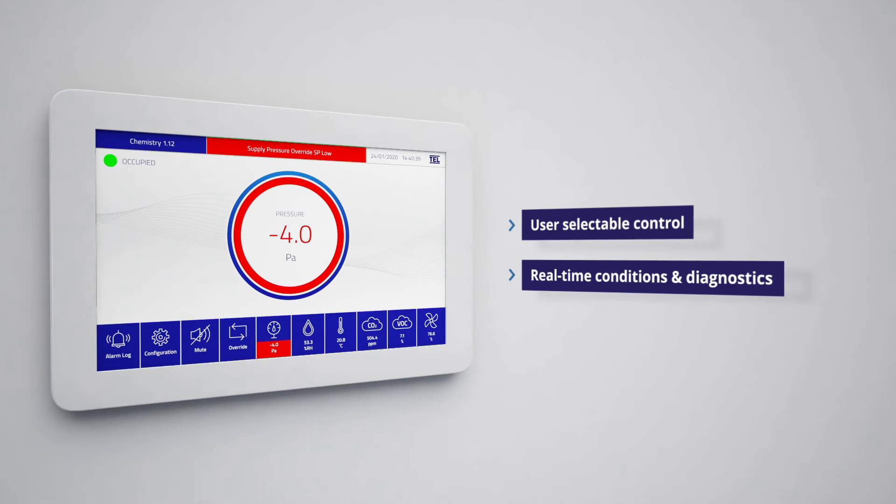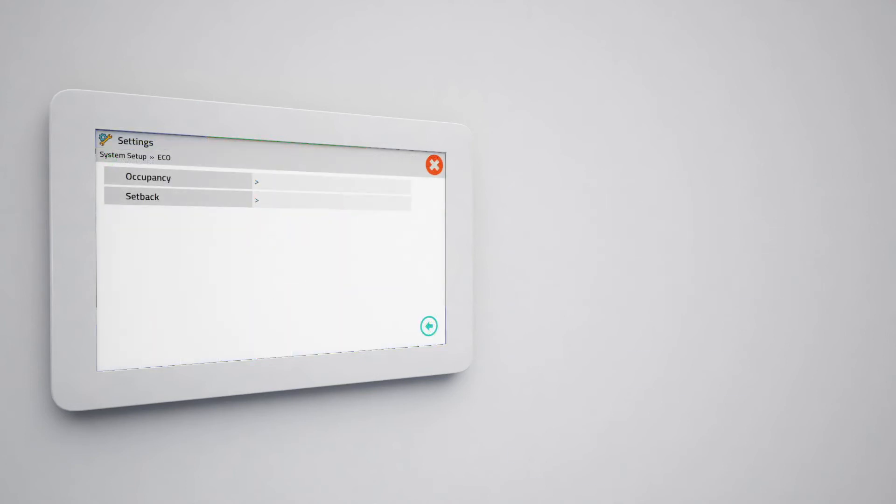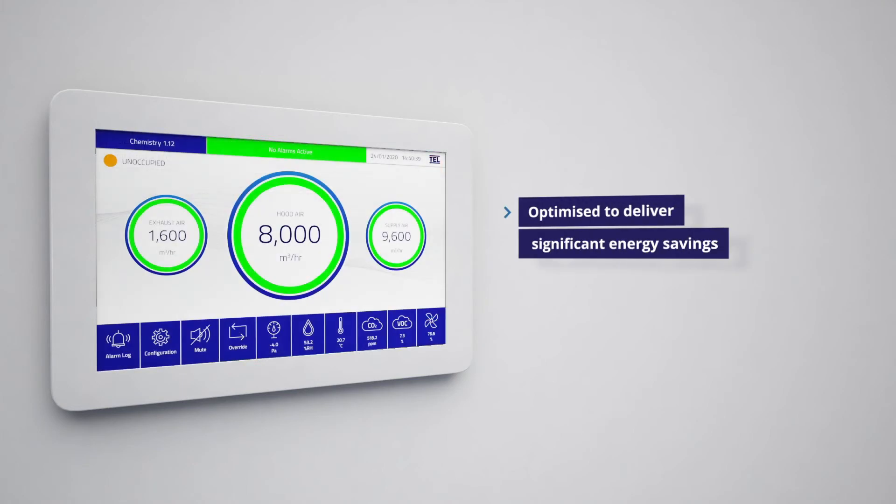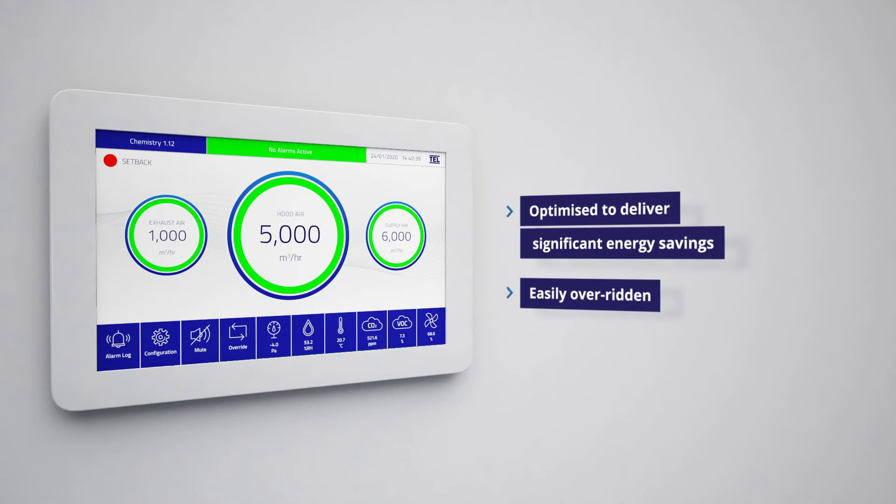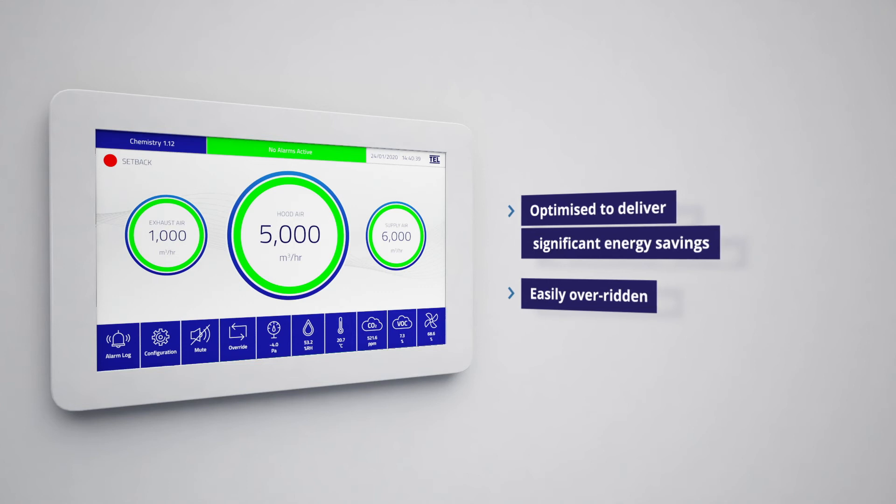Access the eco icon from the configuration screen to discover how the AFA 5000 can be optimised to deliver significant energy savings by reducing flow rates and comfort or air quality set points for times when the laboratory isn't in use. To protect users, the setback mode can be easily overridden by the detection of a user in the laboratory space or by using the override push button on the run screen.